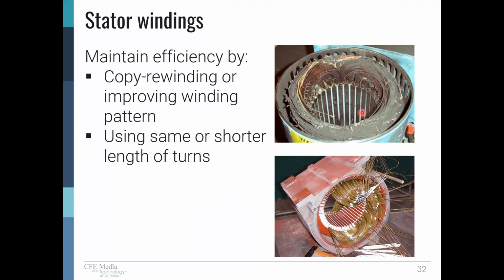We've got that shape, and the advantage of this for the manufacturers is these coils can be inserted by machine. Because they're inserted by machine, they can't get it quite as tight in the slots as you could by putting it in manually. And what many service centers do is they'll convert this winding, or have us in technical support convert the winding, to what we call a lap winding, like what we see down below, where you lay a coil in and you lay the next coil in, and each one overlaps the next, so they don't have a common center. That's called a lap winding. Magnetically, it actually gives better performance. It has less losses, tends to be less noise than the concentric winding. And we can put more wire in the slots typically than the manufacturer can, and also keep the end-turn length controlled, keep it as short as possible.